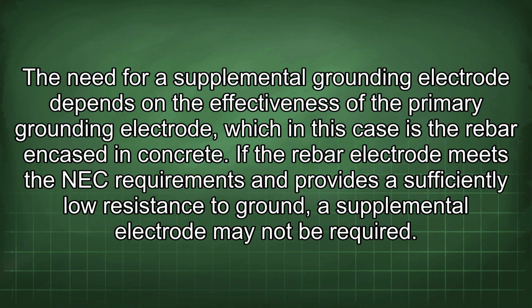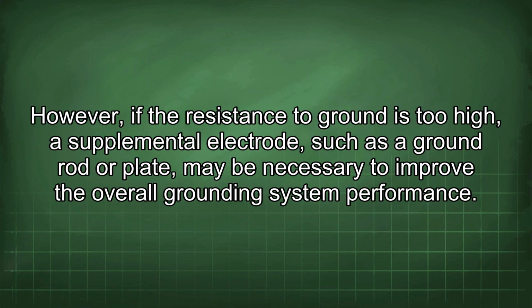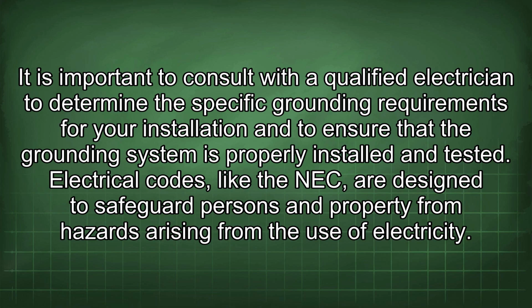The need for a supplemental grounding electrode depends on the effectiveness of the primary grounding electrode, which in this case is the rebar encased in concrete. If the rebar electrode meets the NEC requirements and provides a sufficiently low resistance to ground, a supplemental electrode may not be required. However, if the resistance to ground is too high, a supplemental electrode, such as a ground rod or plate, may be necessary to improve the overall grounding system performance. It is important to consult with a qualified electrician to determine the specific grounding requirements for your installation and to ensure that the grounding system is properly installed and tested.